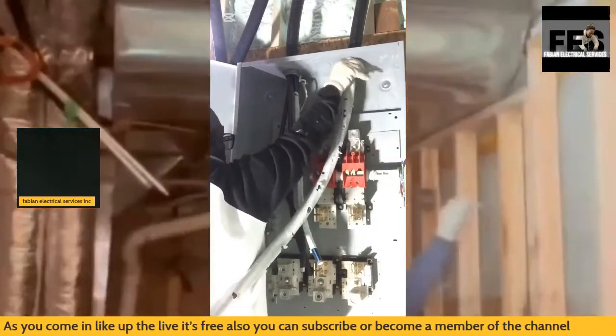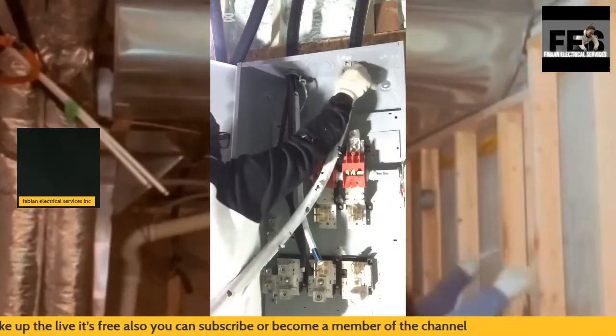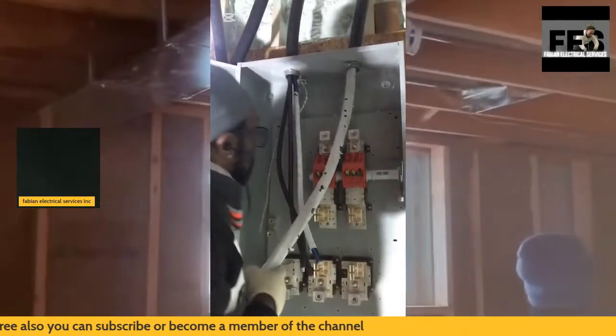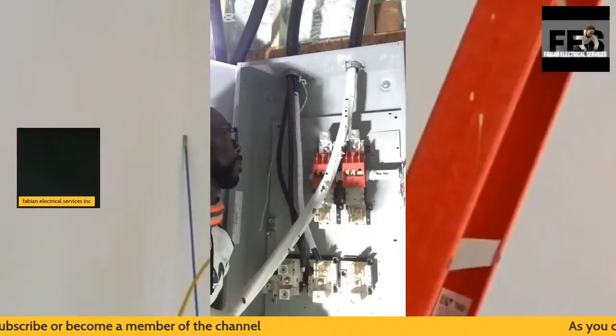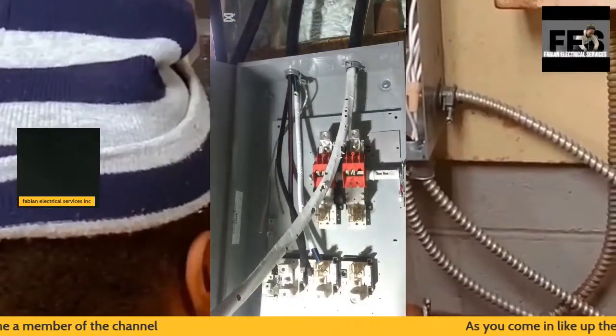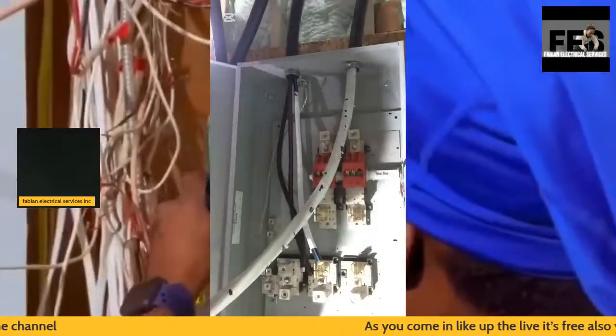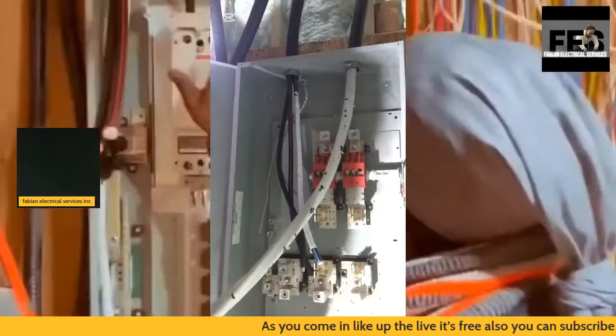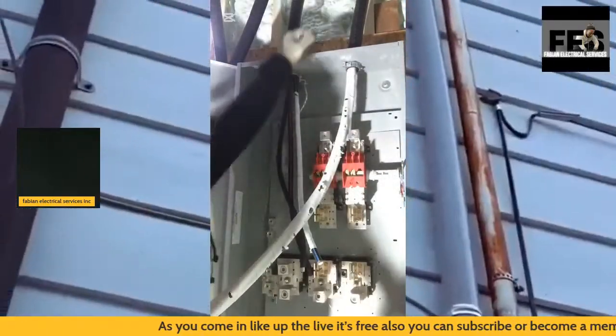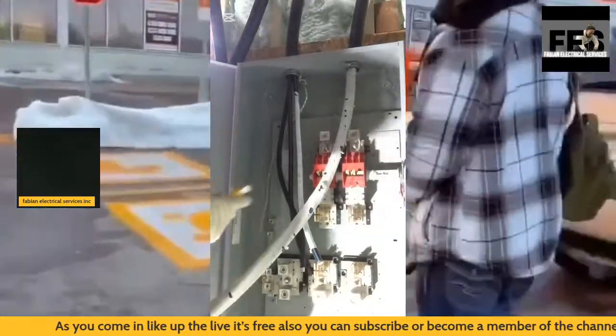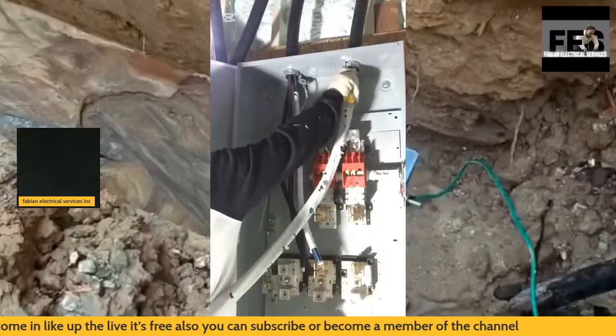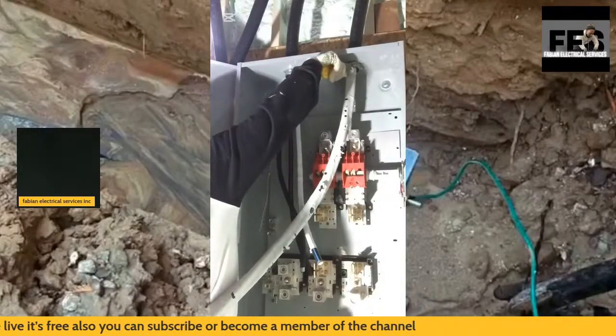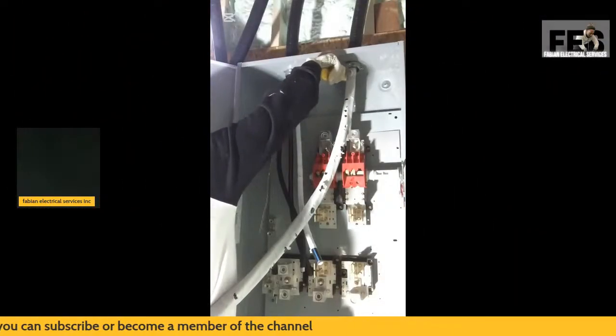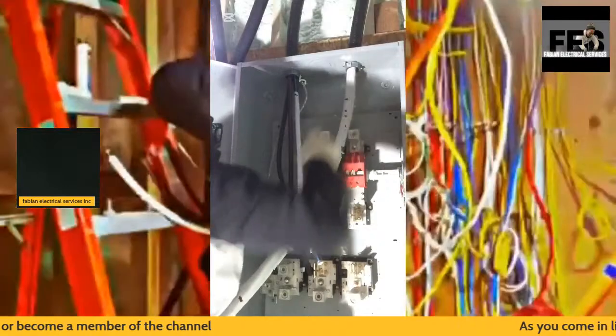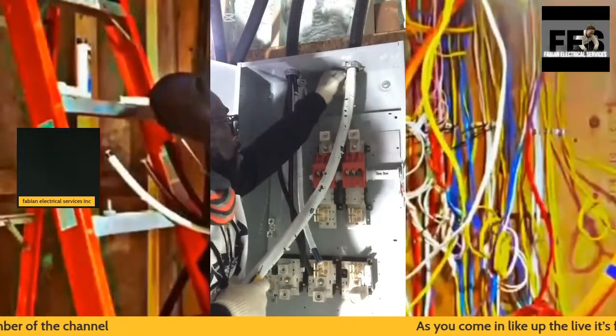So again, the installation reason that the disconnect is here and not at the 400 amp panel is because of the code rule that states anything that's within 5 feet of the electrical panel or the meter base shall have a disconnect, which allows installation of the panel right away.